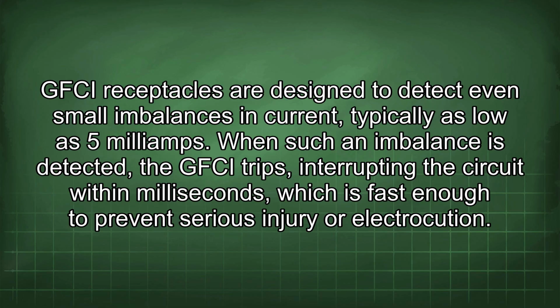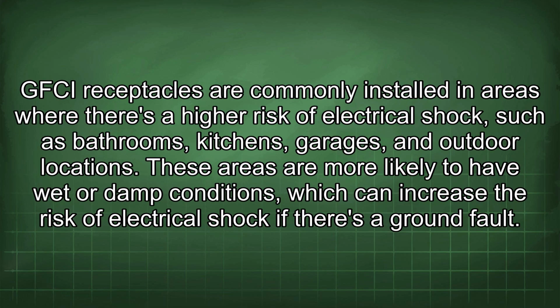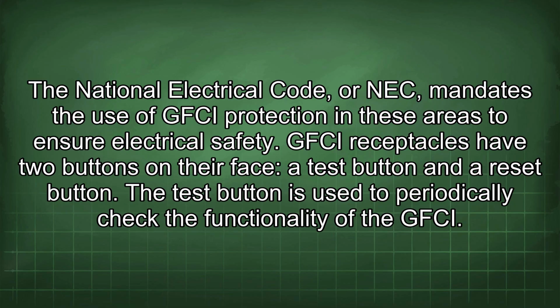When such an imbalance is detected, the GFCI trips, interrupting the circuit within milliseconds, which is fast enough to prevent serious injury or electrocution. GFCI receptacles are commonly installed in areas where there's a higher risk of electrical shock, such as bathrooms, kitchens, garages, and outdoor locations. These areas are more likely to have wet or damp conditions, which can increase the risk of electrical shock if there's a ground fault.